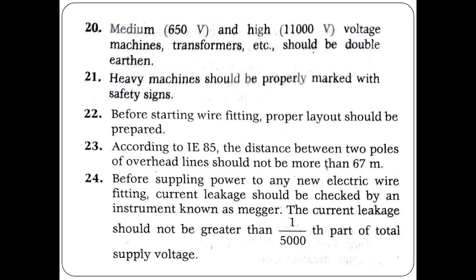Medium voltage (650V) and high voltage (11,000V) machines, transformers, etc. should be double earthed. Heavy machines should be properly marked. Before starting wire fitting, a proper layout should be prepared. According to IE rules, the distance between two poles of overhead lines should not be more than 67 meters.